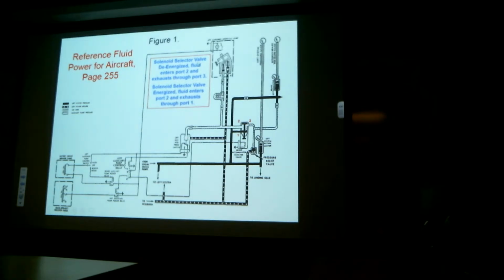It says this: with the solenoid selector valve de-energized, fluid enters from port 2 and exhausts out of port 3. So the fluid comes in from port 2 to port 3 as long as the solenoid hasn't been actuated. And it says with the solenoid selector valve energized, fluid enters through port 2 and is exhausted out port 1. So when we provide electrical power to the coil of the solenoid valve, it pulls this down, so the fluid flow goes from port number 2 through port number 1. We'll talk about this maybe a little bit more in detail next week. The controlling circuit is just an electrical switch. It's a 3-position switch. One of the positions is auto, another position is off, and the other one is a momentary contact for reserve brake. But we'll talk about this next week.